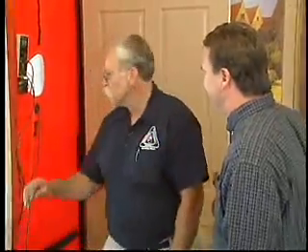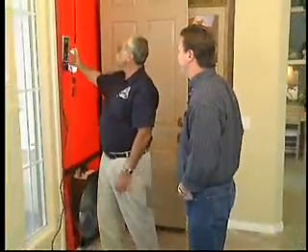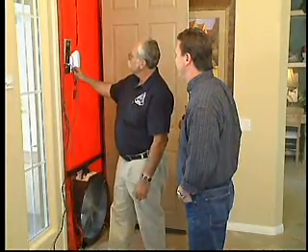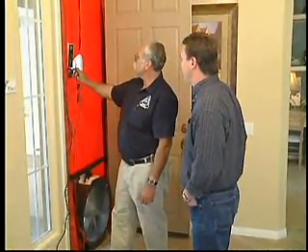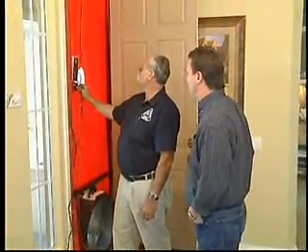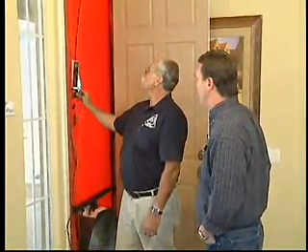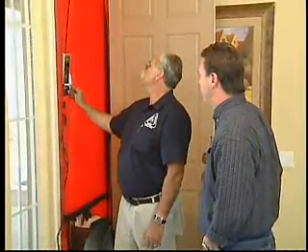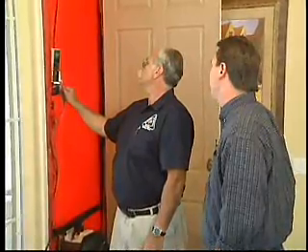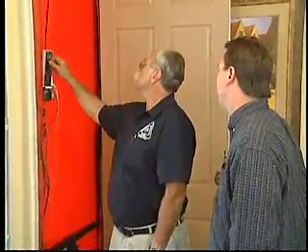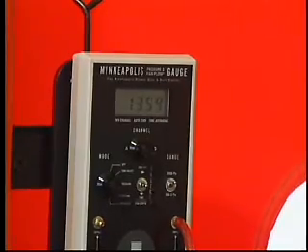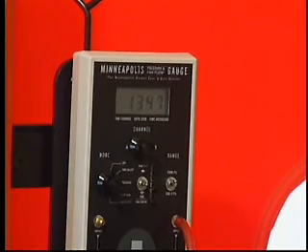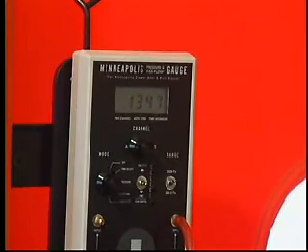And we can test this house, right? Oh, yeah. In fact, let's do that. I'm going to turn on the fans. Here's that membrane I was talking about. This is a manometer. This is a speed control that we can use to turn up the RPMs of the fan. We just bring the fan up to a given pressure. As you can see, Steve, we came in at 1,347 cubic feet per minute at 50 pascals. That's pretty good. Yeah, it is.